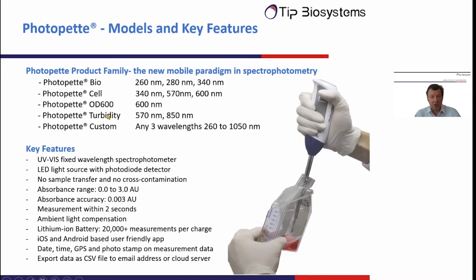So the key features of the device: it ranges from the UV to the visible spectrum, from anything like 260 to 1000 nanometers. Basically, the company can build any custom device with 3 wavelengths in between this range. The light sources are LEDs. There is no sample transfer or cross-contamination. The device has a very large absorbance range, up to OD of 3, with an accuracy of reading of 0.03. The measurements are very fast. It just takes 2 seconds.